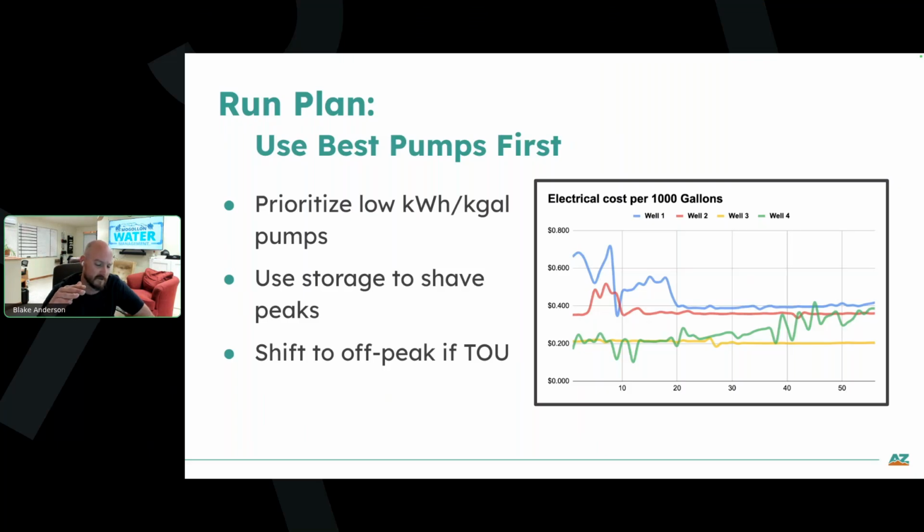So if you can, if your tank is running like a 3-foot deadband, if you can expand that to 4, 5, 6 feet, it doesn't really impact the PSI that much. And so do you need that much storage capacity? Could you use your storage capacity a little bit differently? Could you set up things to run into lag lead function? Could you set up winter and summer operating cycles with different programming functions? Could you use your storage overnight? You know, could you have a well that kicks on in off-peak hours and fills the tank till full before morning, and just runs consistently?